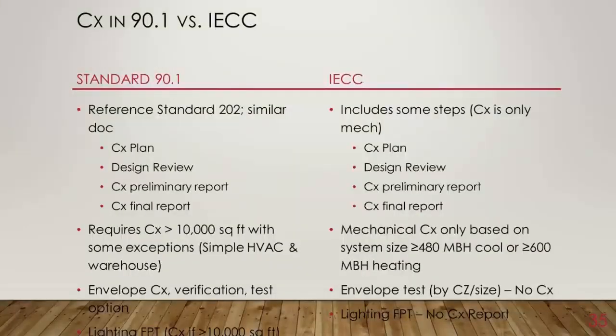So again, I think I've covered most of this. We are referencing Standard 202 as a guideline. We do require a commissioning plan. IECC does, again, only for mechanical. We require a design review that's included in IECC, a preliminary report delivered before the occupancy permit, and then a final report that is delivered to the owner later. That's required, but again, not much teeth once the occupancy permit is issued.